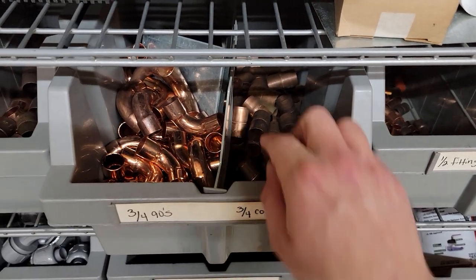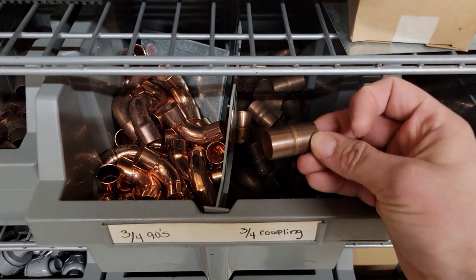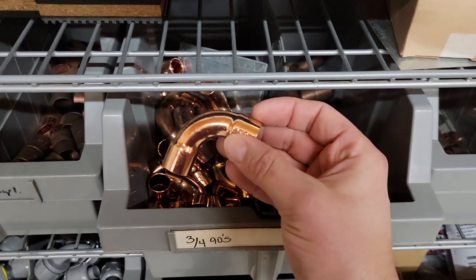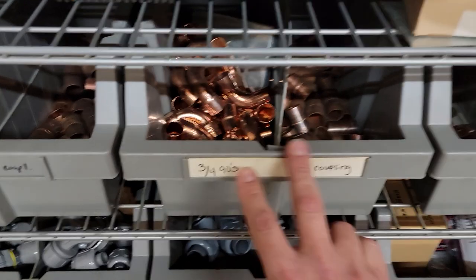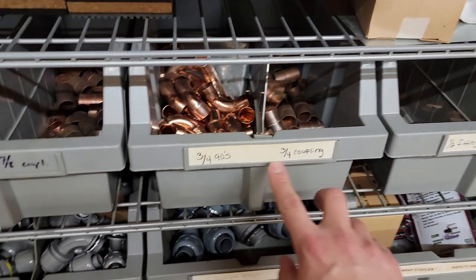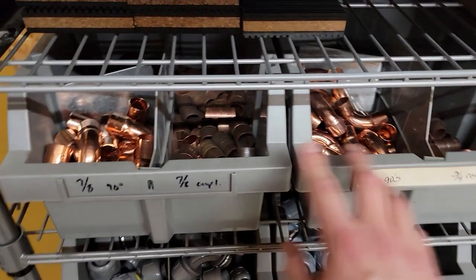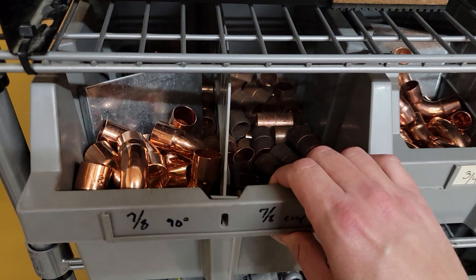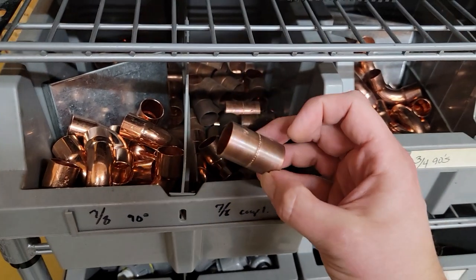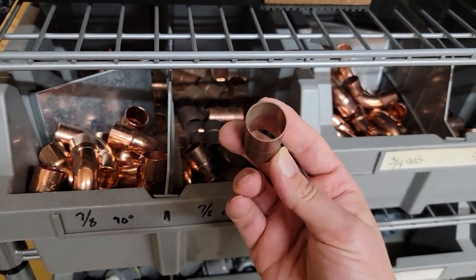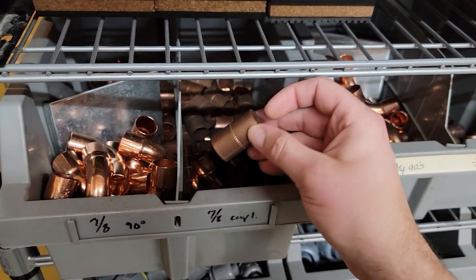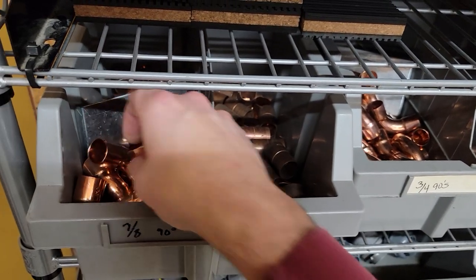This is 3/4. And this is a coupling, okay? And then this right here is, of course, a 90. That's 3/4, usually used for upwards of 3 ton. Anything over 3 ton, you're gonna be using 7/8, okay? So 3.5 ton, 4 ton, 5 ton, it could be 1 1/8, but mostly it's usually 7/8. This is a coupling, and that is a 90.